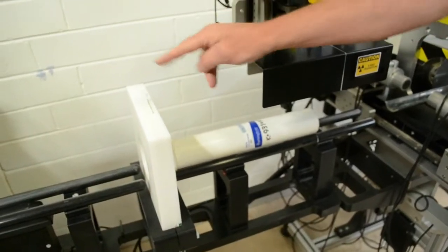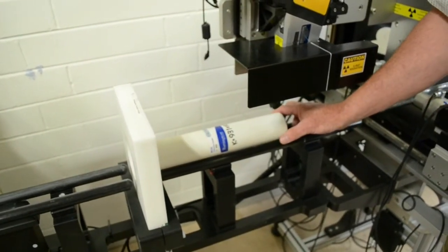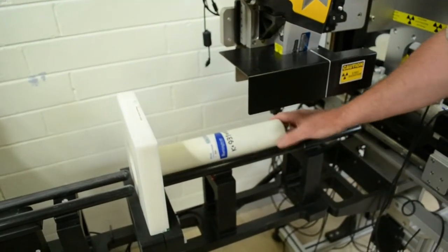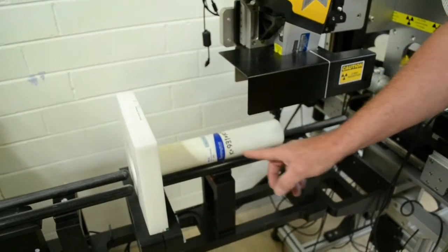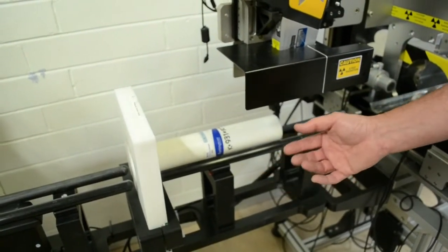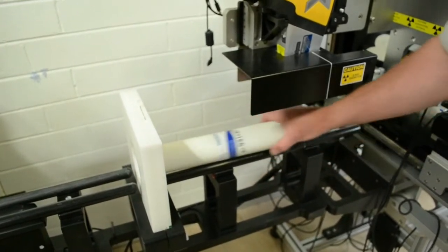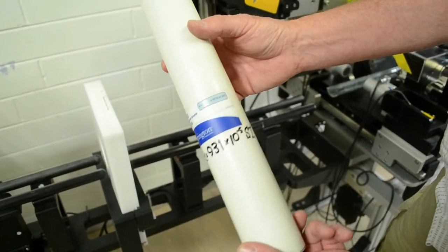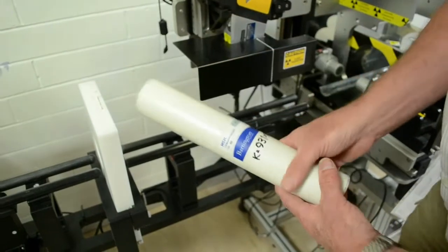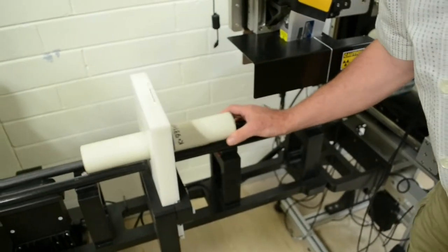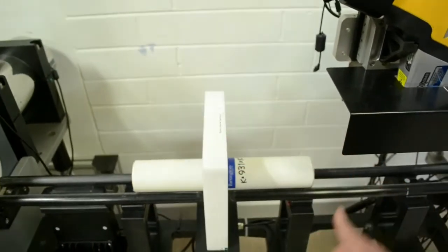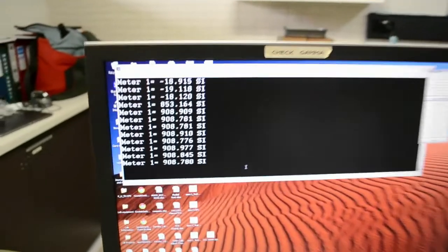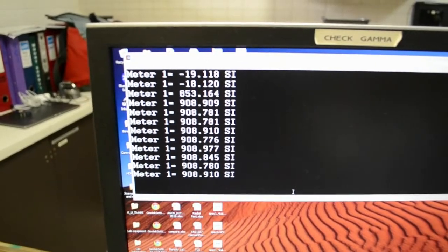For magnetic susceptibility, the loop instrument has a fixed calibration — it is not possible to adjust the instrument itself. We are simply checking that it hasn't drifted too far from the calibration specimen value of 931 by 10 to the minus 5 SI units. Placing the calibration specimen fully in the loop so the magnetic field senses the magnetic material, we're recording 908 to 909.